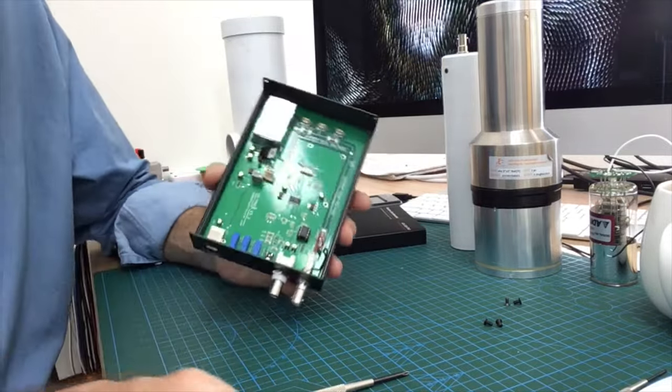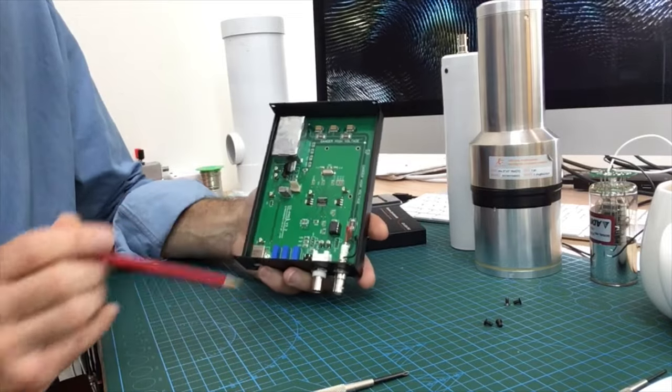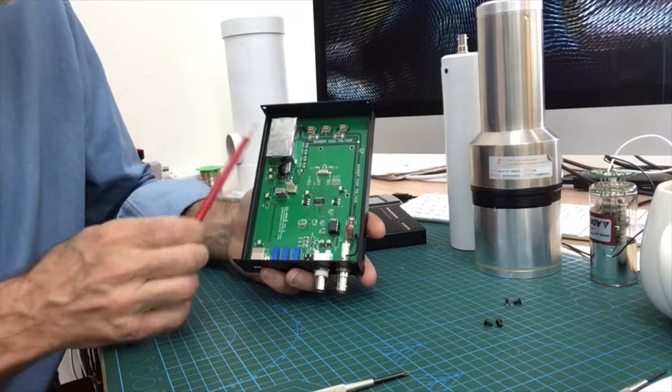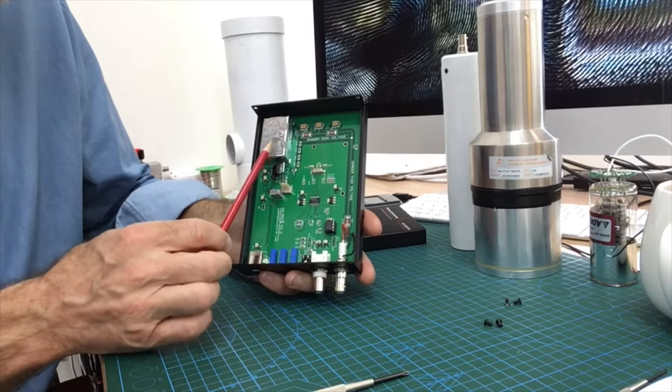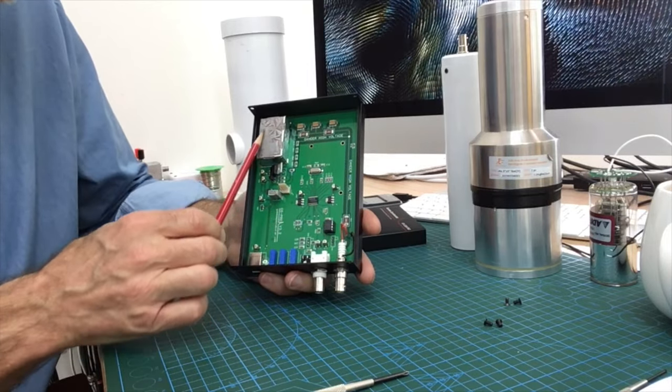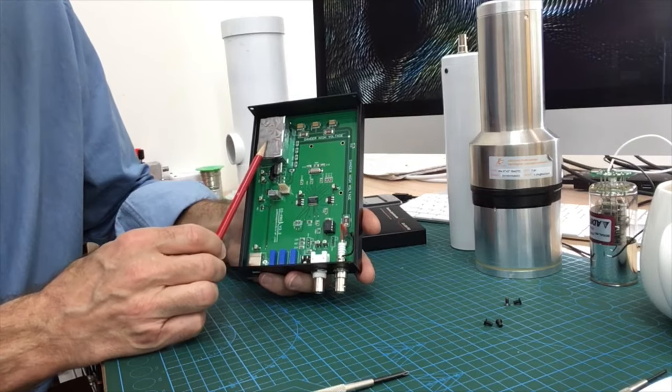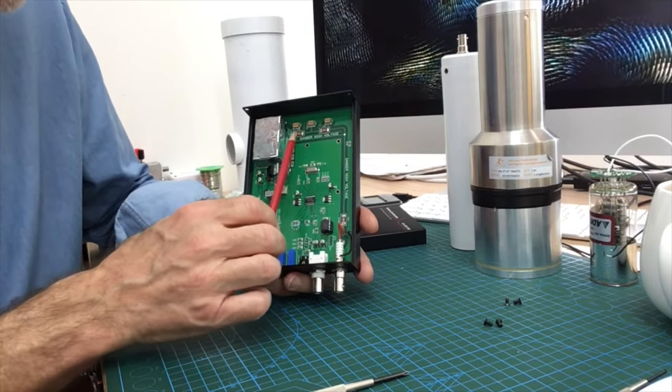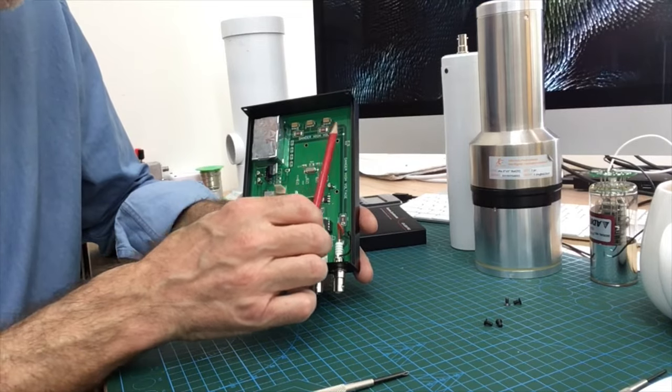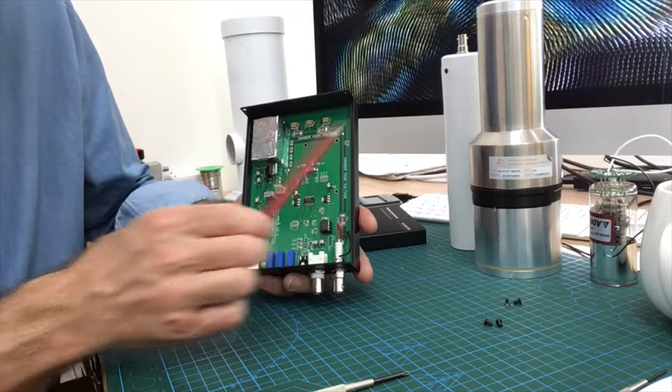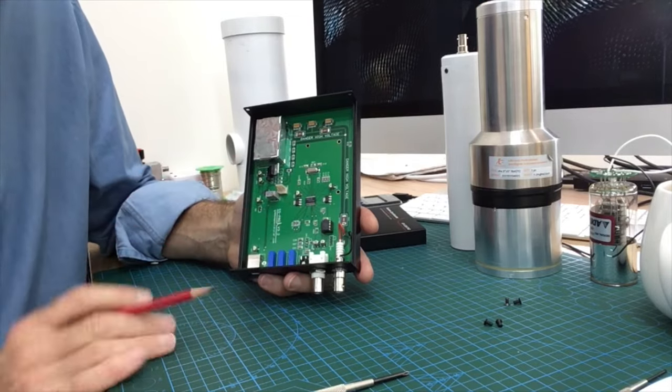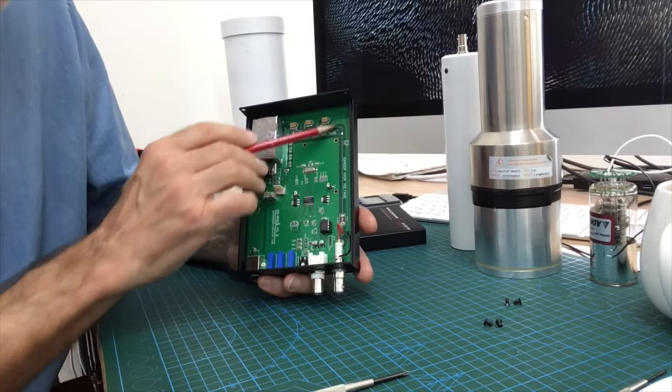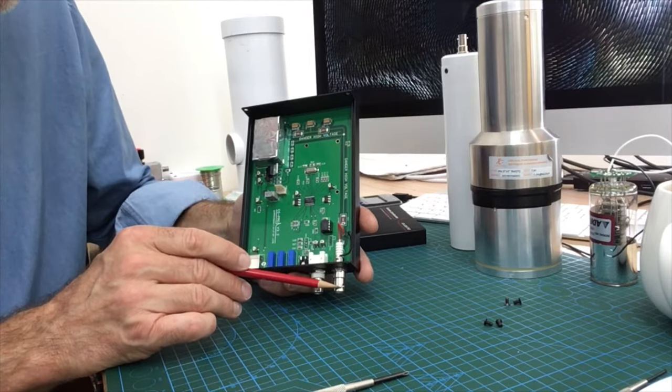And here we can see the basic layout of the circuit. Now over here in the top corner, this is the high voltage supply and that's a little Royer oscillator. It comes out here, goes through some smoothing capacitor, and this is an RC circuit that smooths out the ripples and gives a very steady high voltage signal. It comes down along here and goes to the high voltage SHV connector.